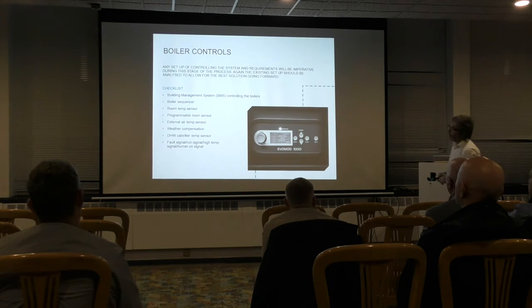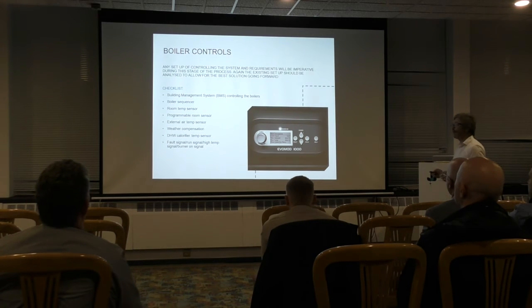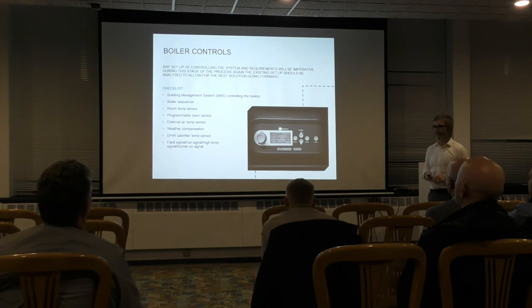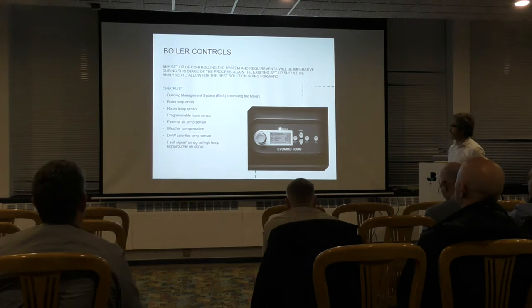And then moving on from that, look at the controls. Older systems, you're going to have pretty antiquated controls, I'm pretty damn sure. I think you'll be fairly lucky if you went into an old plant room and you're going to have lovely new BMS systems sitting in there. If you have, brilliant, the boilers can just hook up to the BMS system, the BMS can take care of everything. But I suppose really just be aware of what that client's after. If they do want to look at putting a new BMS in, then yeah, great, let's go for that.